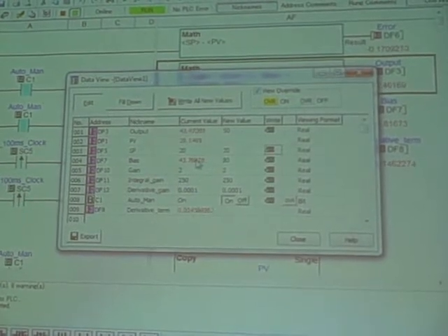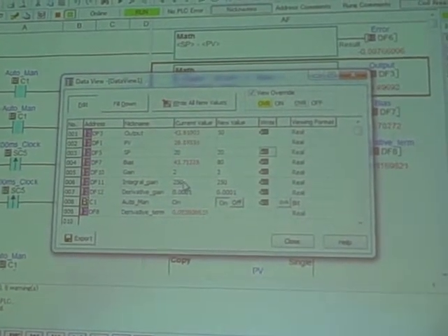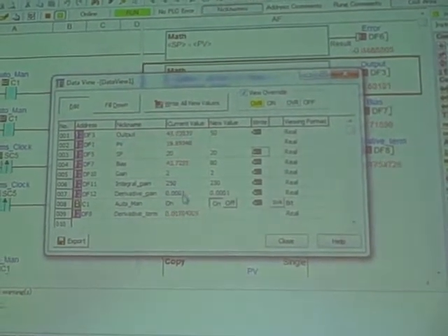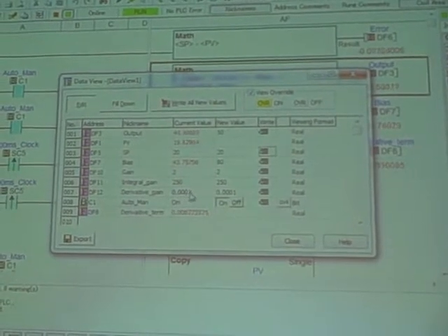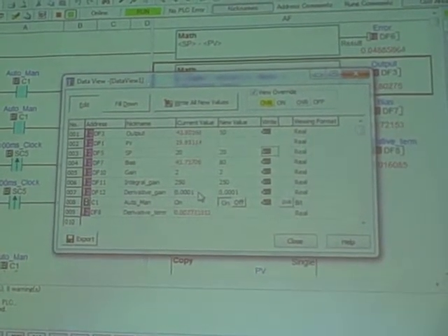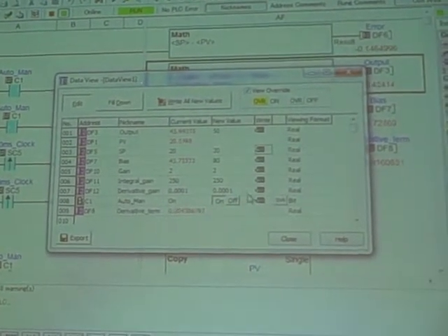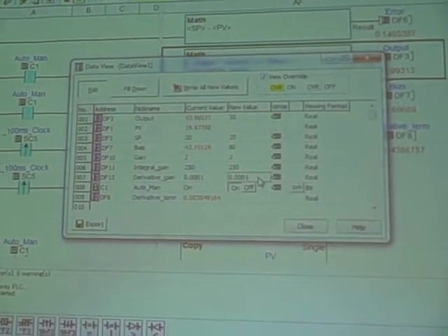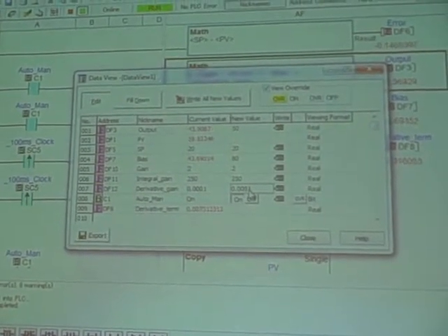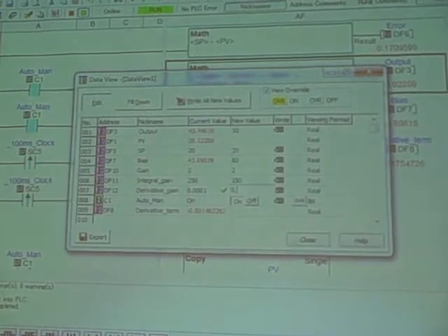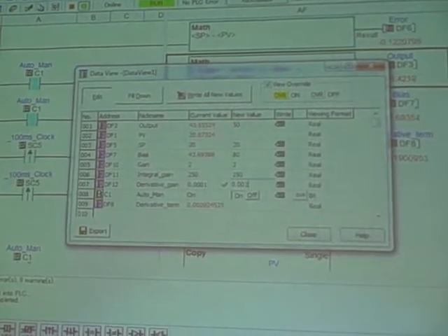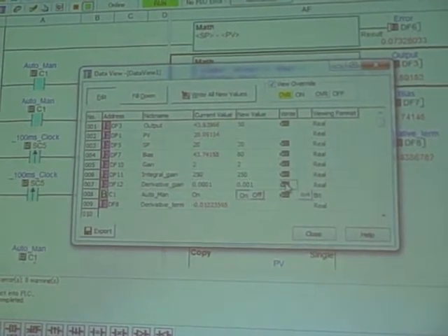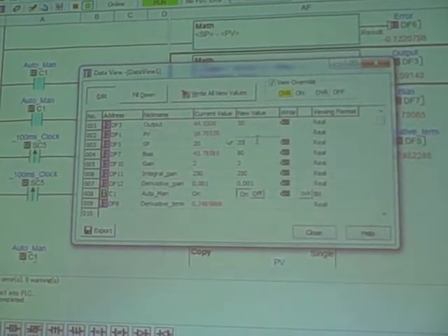There's our bias term right there, our gain, our integral gain in repeats per minute, our derivative gain in minutes. It's a very, very small number because this is an inherently fast process. We don't want anything too big. If I take away just one of those zeros, I think we found 0.001, I think we found that it kind of blew up on us.